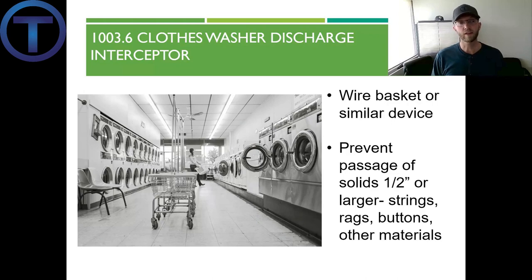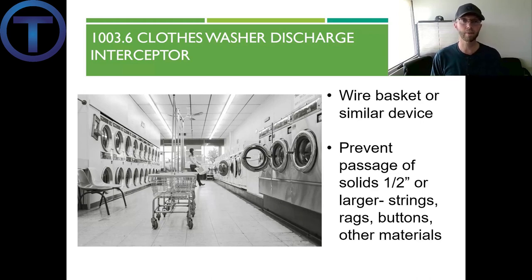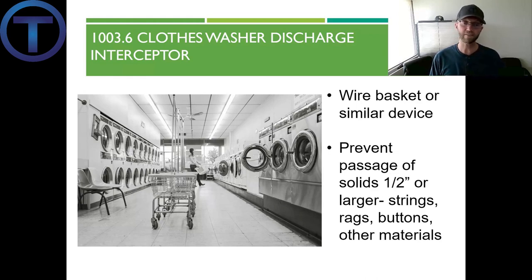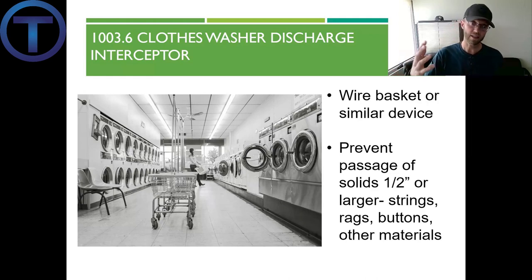Section 1003.6 talks about clothes washers. The discharge from those can often have string, lint, buttons, and who knows what else people put in their pockets — we need to have an interceptor for that. Especially in a commercial laundromat, there is a requirement for a wire basket or similar device that can prevent the passage of solids that are a half inch or larger — strings, rags, buttons, whatever can be pumped out of a washing machine but clog the drains.